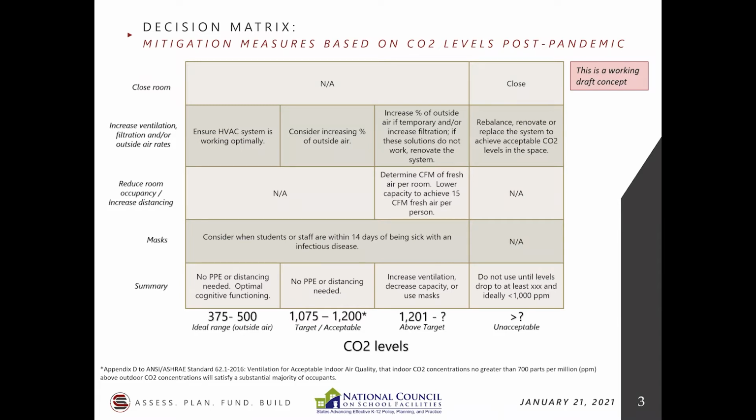Typically carbon dioxide concentrations are going to increase throughout the day. And if you're lucky, in a perfect world, you're going to meet what we call a steady state, or an equilibrium value. Often that does not occur. And so the assumptions directly tying carbon dioxide to the amount of ventilation are tied to you meeting steady state. What I mean by that is that the carbon dioxide level has to level off in the classroom for it to be meaningful. Now, the problem with that is that within the 6-7 hour occupied day within a classroom, you may not meet that equilibrium.